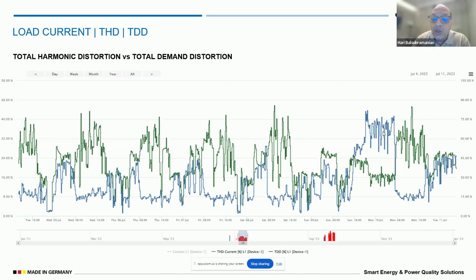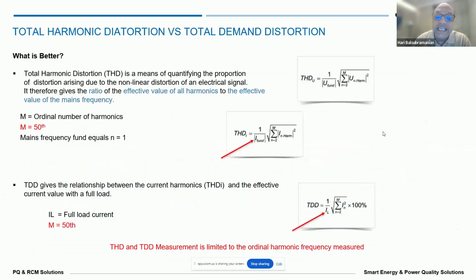So we have the total harmonic distortion and total demand distortion, which we need to understand so that we can take appropriate action. Giving a solution with total harmonic distortion cannot give us the right solution. This is my opinion, and we can always check this out. But total harmonic distortion is comprised of all the harmonics built in. So when we are measuring THD or TDD, it is very important for us to know up to what frequency or what harmonic content this THD is calculated. This is very, very important.